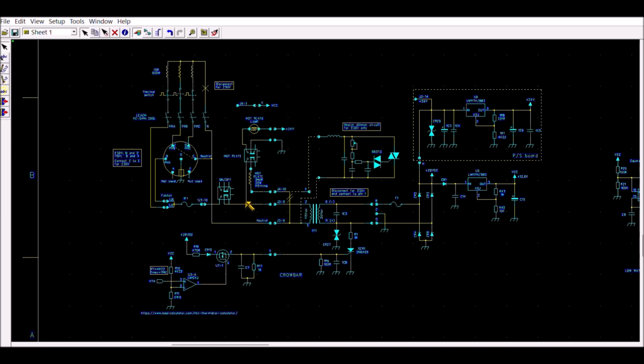The voltage of 115 volts is fed to this transformer. The secondary is approximately 20 volts. You can see the hot plate also, which is connected to phase A through this switch here. There is also a lamp connected to 24 volts, which is activated at the same time as the heaters of the hot plate here. I have measured a resistance of 390 ohms. So the power is approximately 33-34 watts.